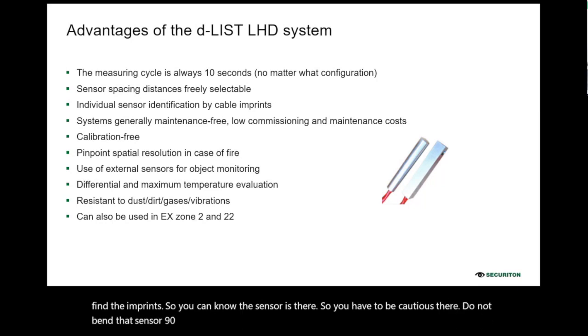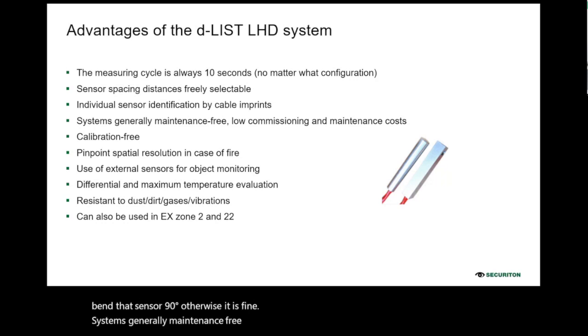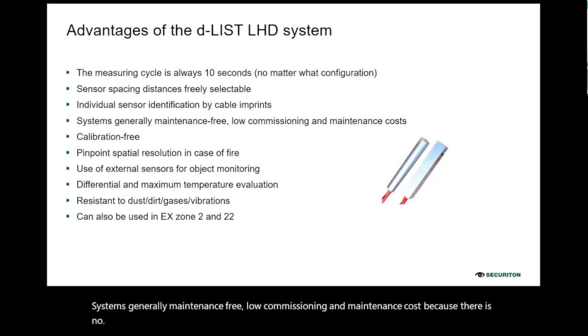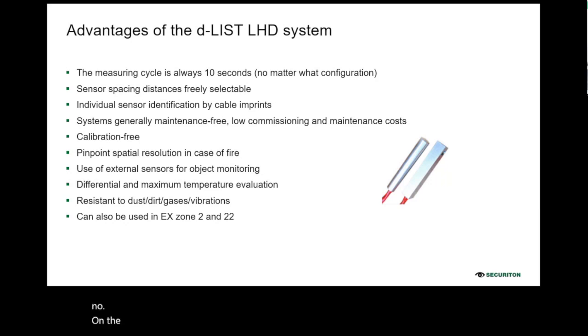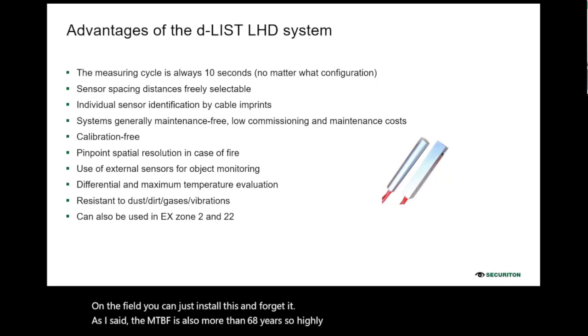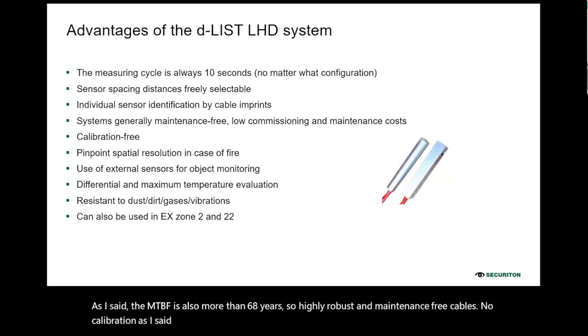Otherwise, it is fine. The system is generally maintenance free, with low commissioning and maintenance cost, because there is nothing to do on the field. You can just install this and forget it. As I said, the MTBF is also more than 68 years. So these are highly robust and maintenance-free cables. No calibration. As I said, no software is needed. It can give pinpoint spatial resolution in case of fire because you have sensors inside the cable.